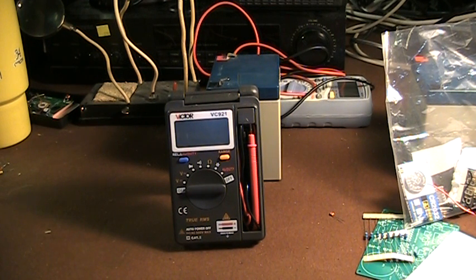First of all, a true RMS multimeter enables you to measure AC sources that do not output a nice sinusoidal waveform, such as your utility power. If you're working with most computer-grade uninterruptible power supplies, or you happen to be working with DC to AC power inverters, most of the less expensive types output modified sine wave AC waveforms. And these will cause a regular average responding multimeter not to work correctly. It'll give you the wrong voltage indication. The true RMS multimeter does not suffer from that problem.